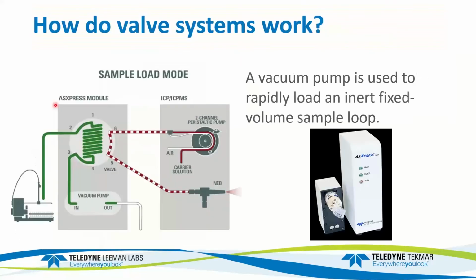The ASX approach is a little bit different. So here's the ASXpress. There's a vacuum pump inside this module, and we'll look at the module in a minute. And then what happens is, when the sample is being loaded, the peristaltic pump is essentially bypassing where the sample is and going directly to the nebulizer. So there's a reservoir, in this case of kerosene, which is feeding this. And when the instrument is not running samples or not analyzing, this is what it's doing.